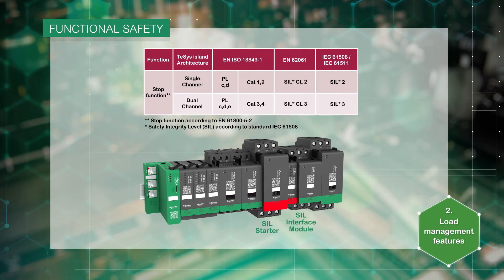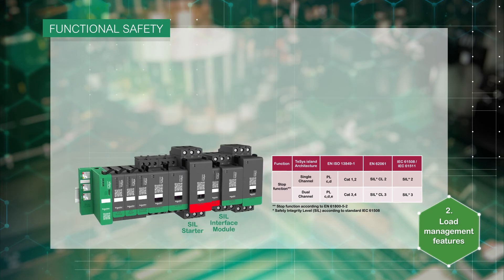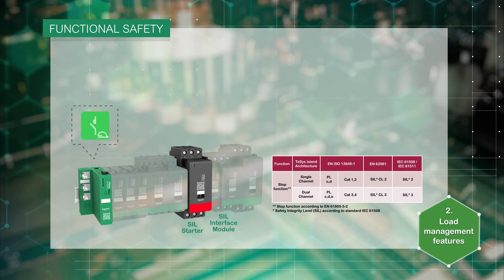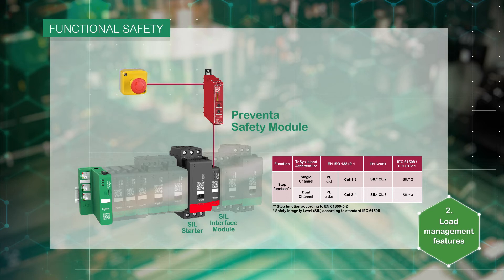When required, functional safety is achieved thanks to SIL starters and the SIL interface module in compliance with main standards. The stop function is achieved by pure electromechanical means without any digital communication or bus coupler involvement. The SIL starter provides the same functions as the standard starter plus the ability to build the safe stop configuration. The user can manage SIL groups, with one SIL interface module per group, which serves as the interface with the external safety relay.